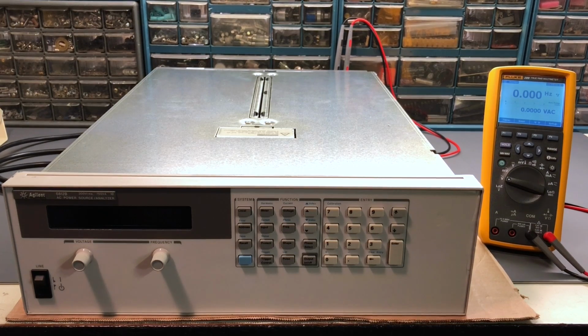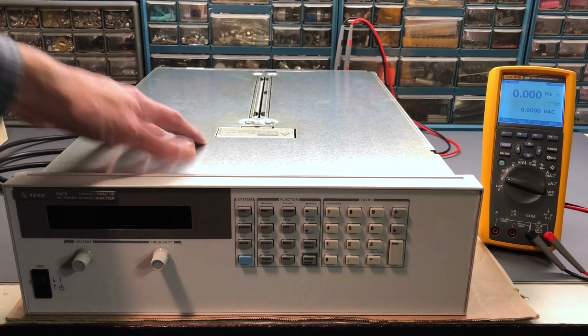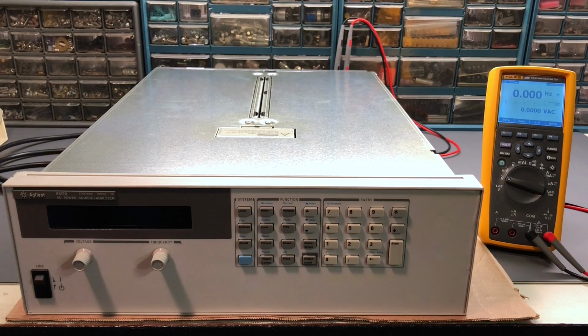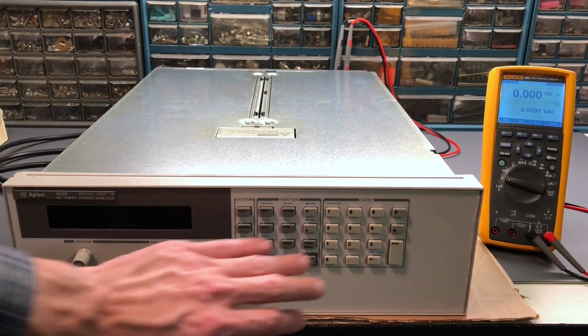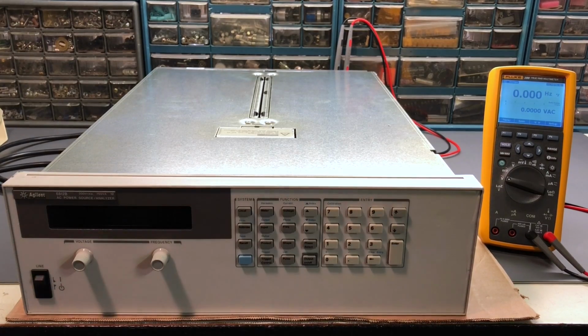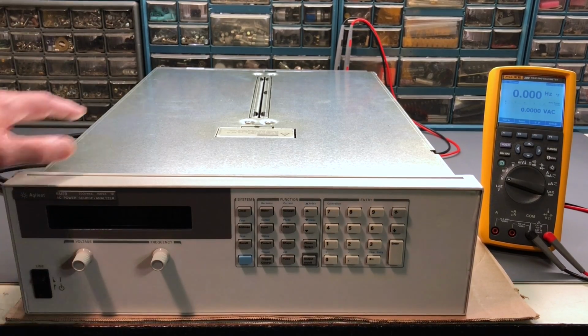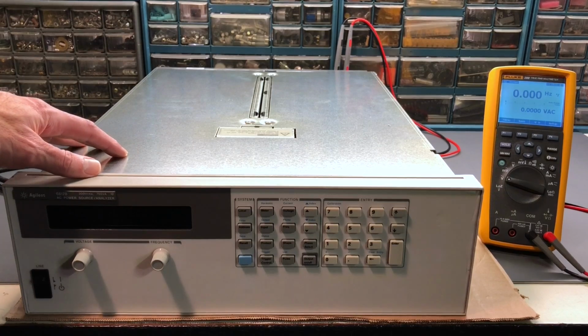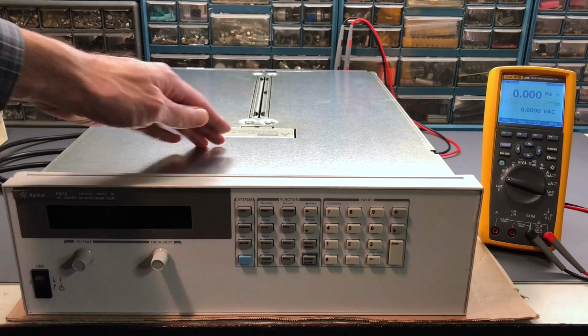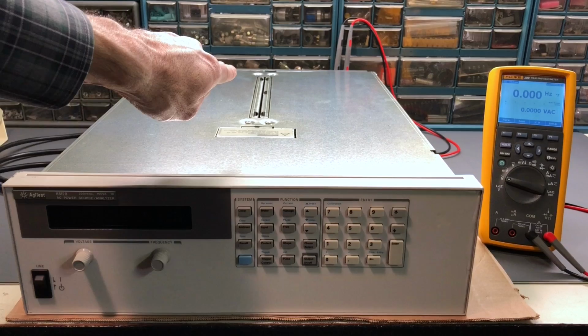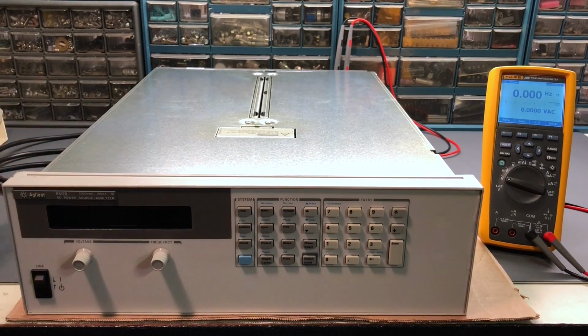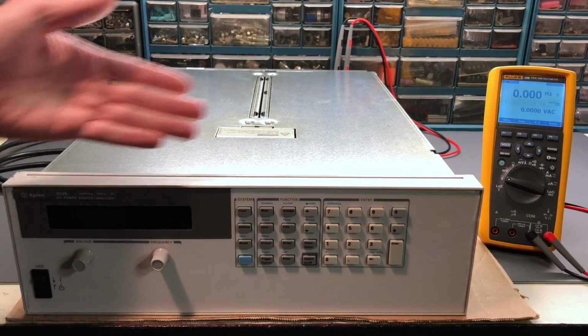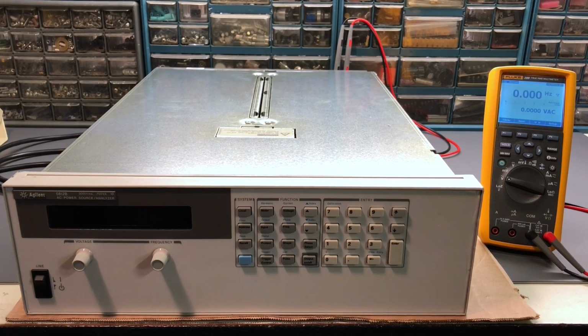Okay, let's see if the 6812B AC power source will power up and function correctly. I've reinstalled this inside top cover on the instrument just as a safety measure. There are no internal adjustments on this instrument, so if it does need any type of adjustment, it would all be done from the calibration on the front panel over here. Again, as a safety measure, this has been reinstalled. Also, this will help the cooling because the fan blows the air down the heat sinks and exhausts out the back, but with this top cover on it, make sure the air is drawn in on the sides and then the air passes over the components correctly internally.